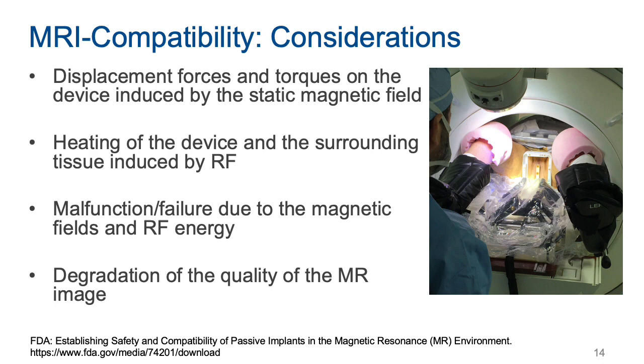In designing the robot for MRI-guided robotic biopsy, it is important to ensure the MRI compatibility of the device. There are 4 things to consider. The first is the displacement forces and torques on the device induced by the static magnetic field. It can shift the device accidentally, causing injury to the patient and the physician. The second is the heating of the device and the surrounding tissue induced by the RF and the gradient field. The third is potential malfunction or failure of the device due to the displacement forces and the torques, or the eddy currents in the internal circuit induced by the magnetic field. Finally, the degradation of the quality of the MR image, which can make it difficult to navigate the procedure.